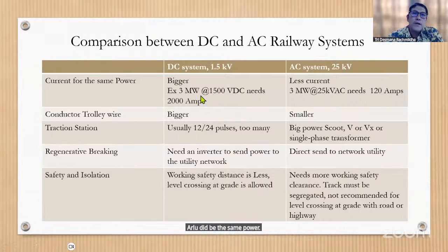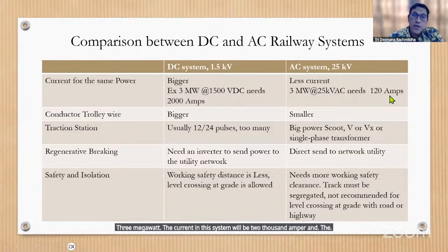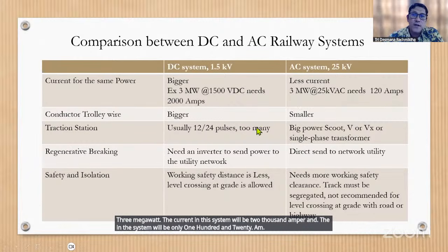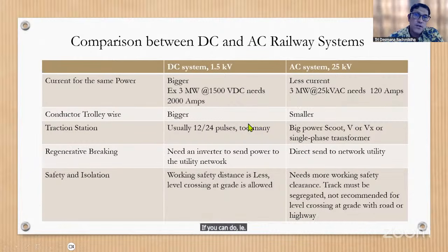For example, at 3 megawatt, the current in the DC system will be 2000 ampere, and in the AC system only 120 ampere. It means that if we calculate the losses in the contact wire, we will have lower losses in the AC system, of course, because we use higher voltage.